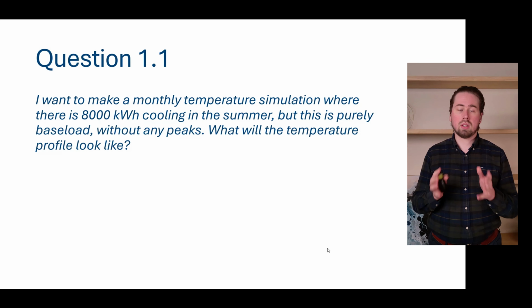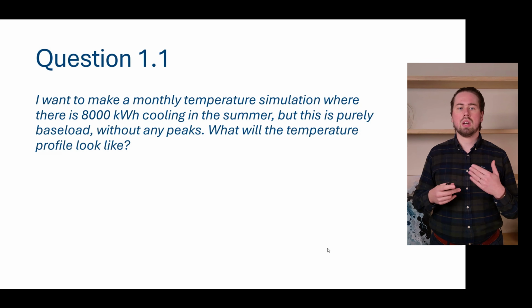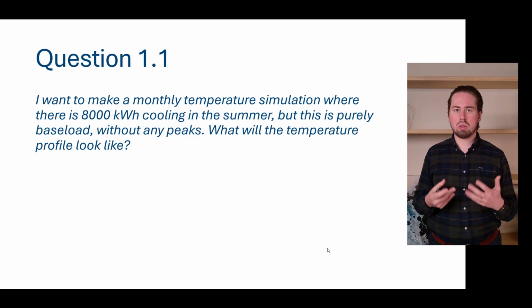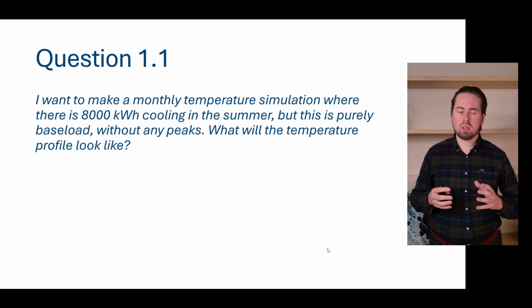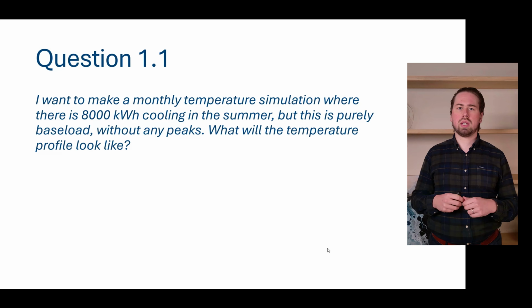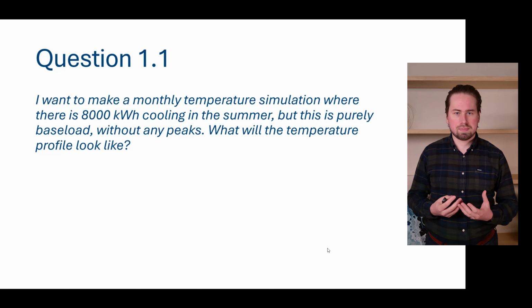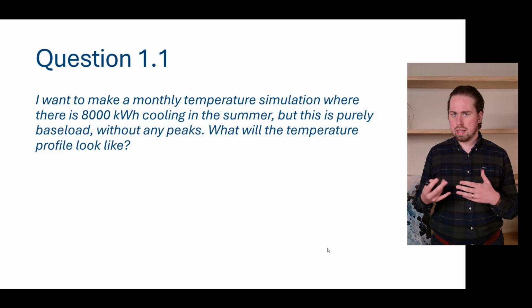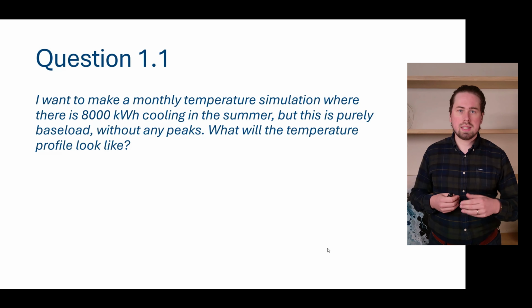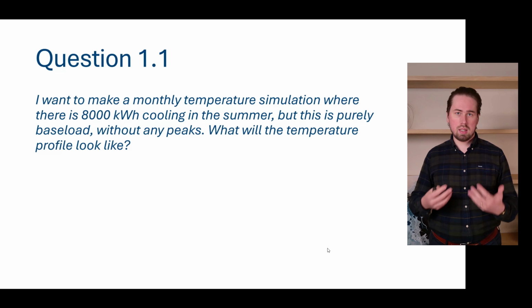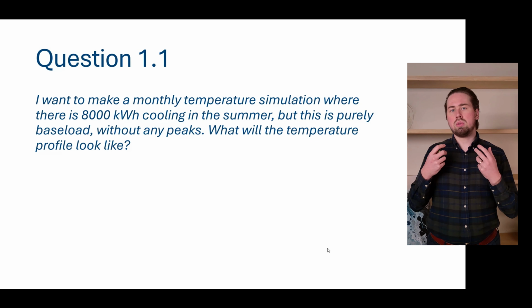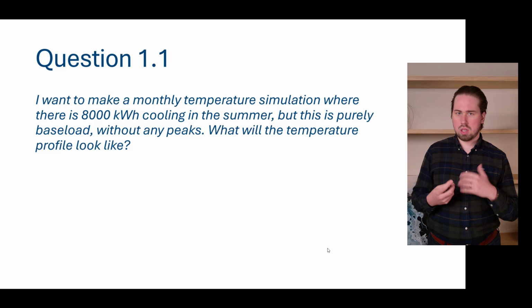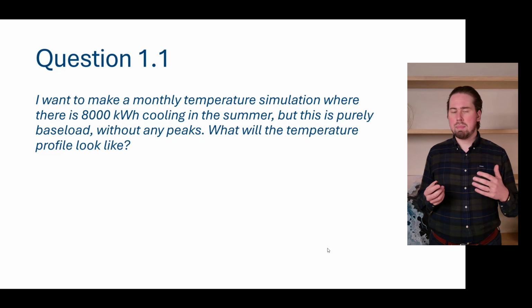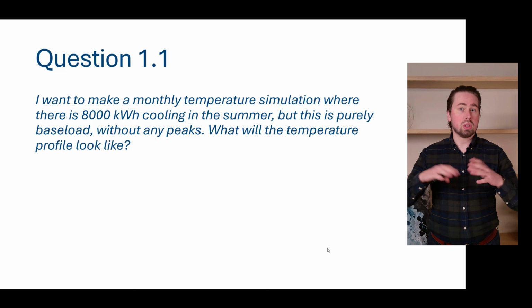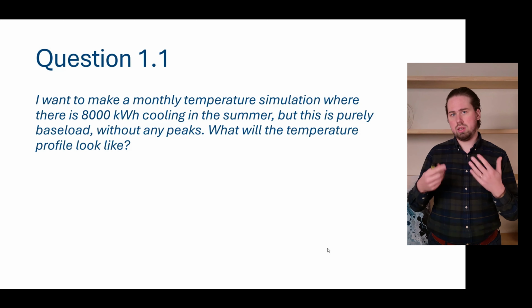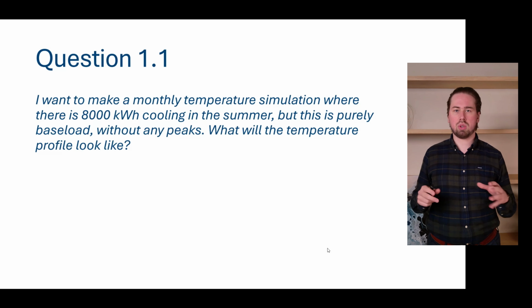So, question 1.1 was about how a temperature profile would look when we assume we don't have any peak powers for cooling, we just have a baseload power. So how would that profile look? Of course, it's really easy to just put it into GHE tool and see. But if you don't have any peak powers on a monthly profile, what basically happens is you just have your monthly energy load, because your yearly energy load gets converted to a monthly profile.